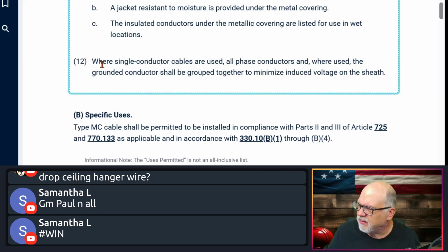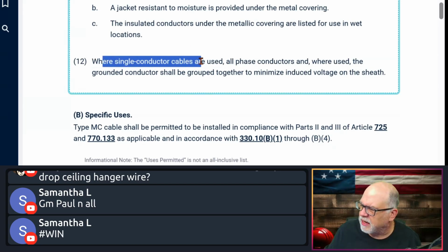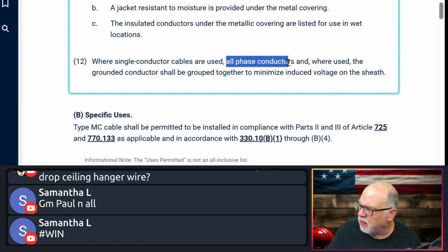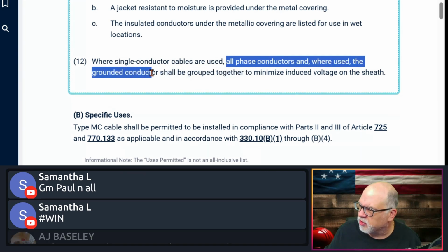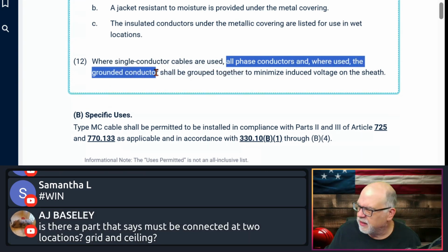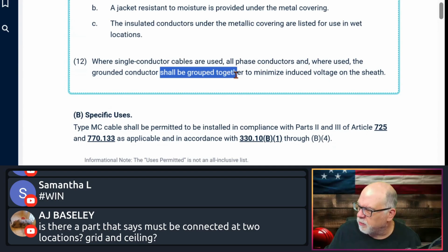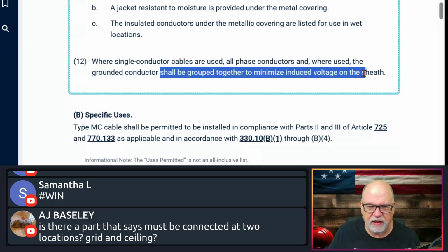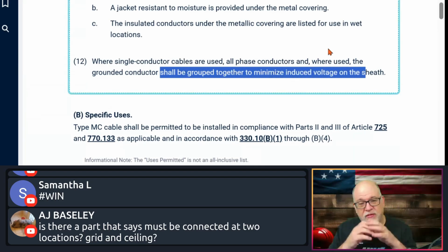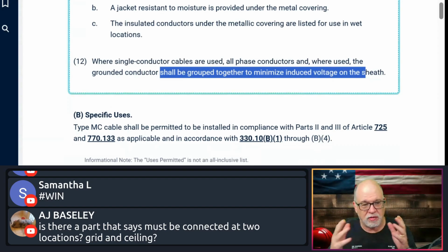Okay. And if you're using a single conductor type, all phase conductors and the grounded conductor, the neutral, shall be grouped together to minimize induced voltage on the sheathing. Running them in close proximity, just like you would do with a single conductor MI. Now, they do make MI with multiple conductors in there as well.